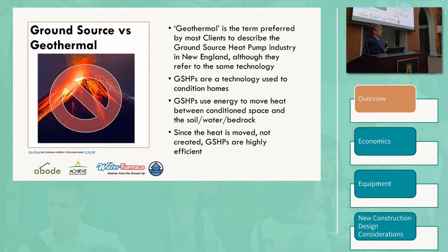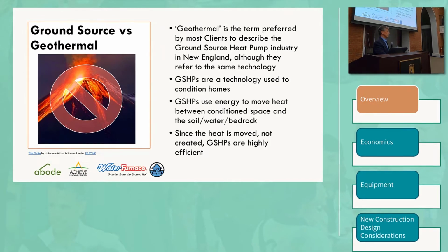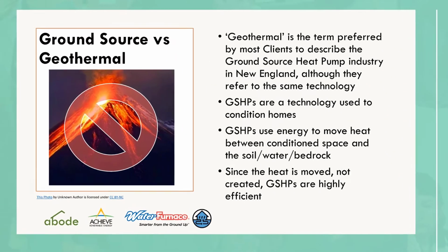And the ground source heat pump devices we use move heat to and from the structure to provide either heating or cooling. And because the heat pump is not creating the heat, but instead moving it from one location to the other, the efficiency of operation can be much higher than with a conventional or fossil fuel system.